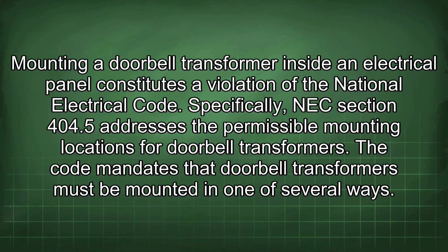Mounting a doorbell transformer inside an electrical panel constitutes a violation of the National Electrical Code. Specifically, NEC Section 404.5 addresses the permissible mounting locations for doorbell transformers. The code mandates that doorbell transformers must be mounted in one of several ways.